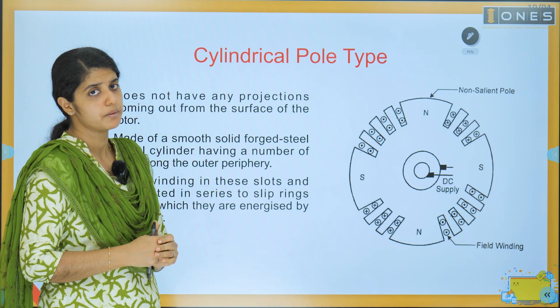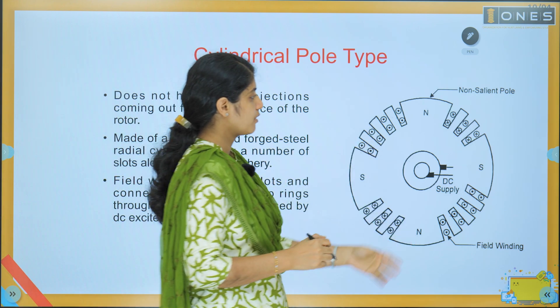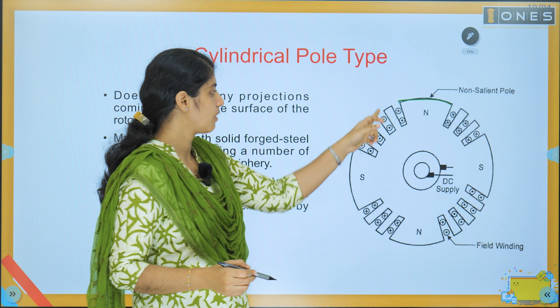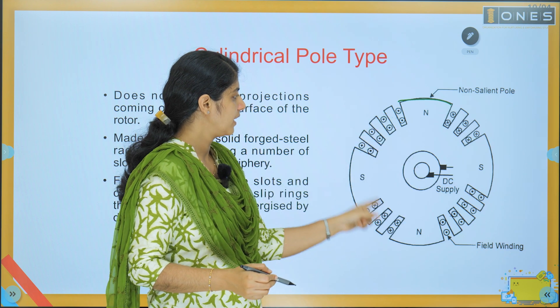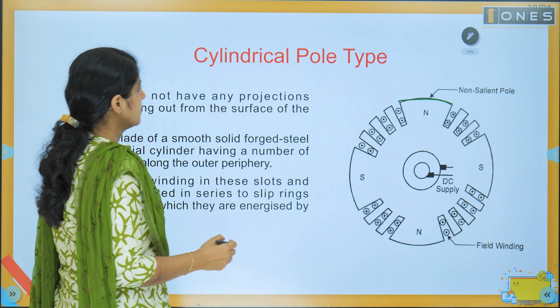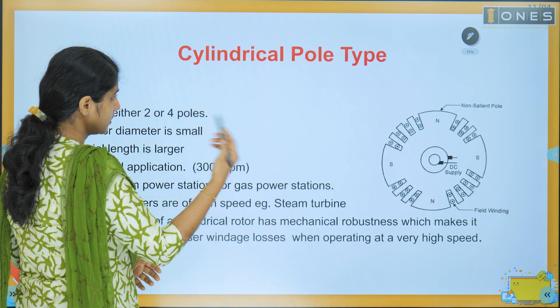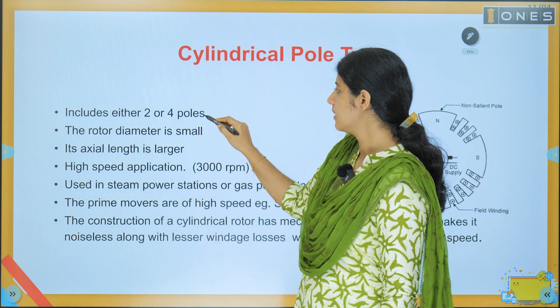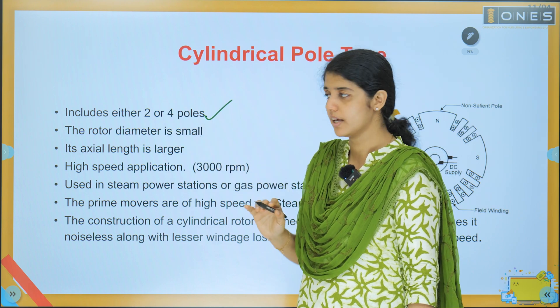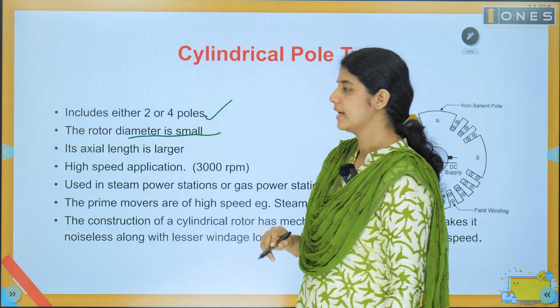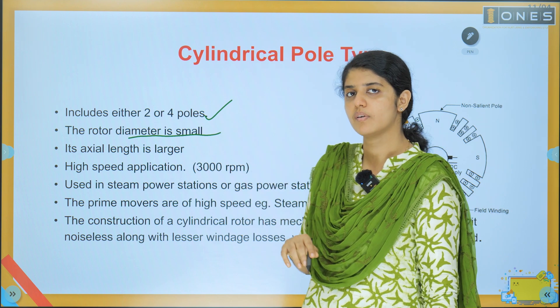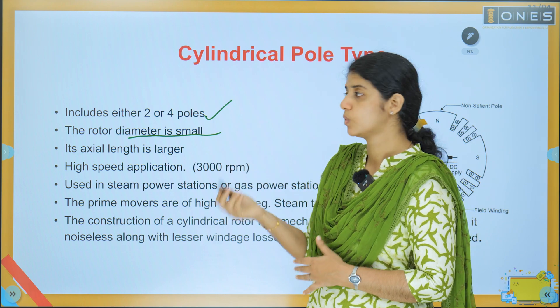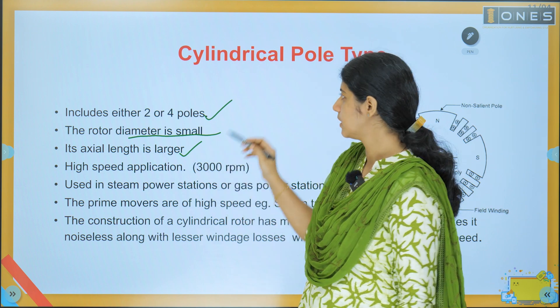The next structure is the cylindrical pole structure — a four-pole structure. The rotor surface is slotted, and the slots place the field windings to create north or south poles. These features are opposite to the salient pole. The cylindrical pole has fewer number of poles — two to four poles — and the rotor diameter is small.